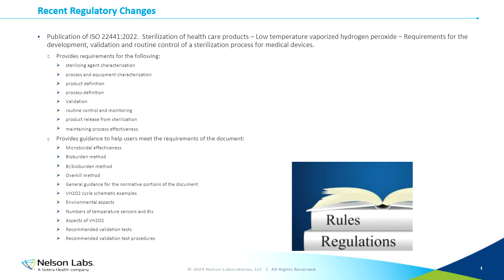So that document, first of all, provides requirements for the development, validation, and routine control of a vaporized hydrogen peroxide process, and includes the items that you'll see on the first slide here, which include sterilization agent characterization, process and equipment characterization, product definition, process definition, validation, routine control and monitoring, product release from sterilization, and maintaining process effectiveness. In addition to the requirements that it provides for those using this form of sterilization, it also provides guidance on a number of topics. That guidance includes bioburden-based validation methods, as well as the overkill method, which tends to be much more commonly used.